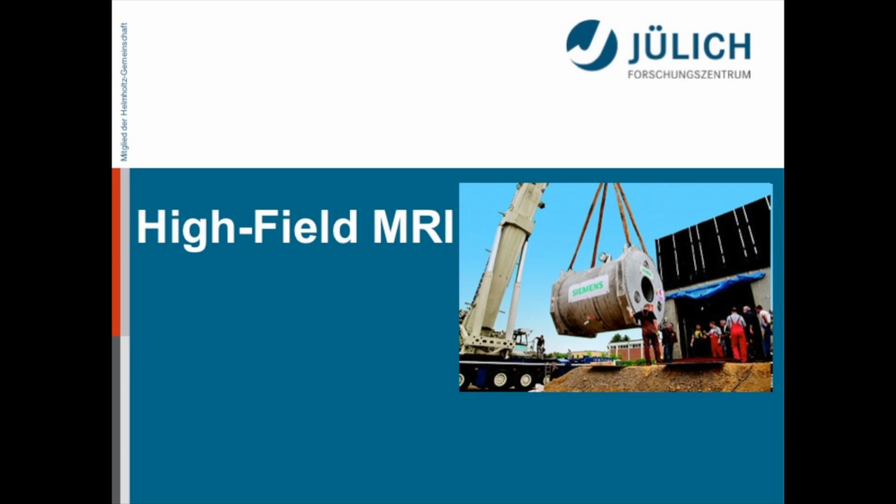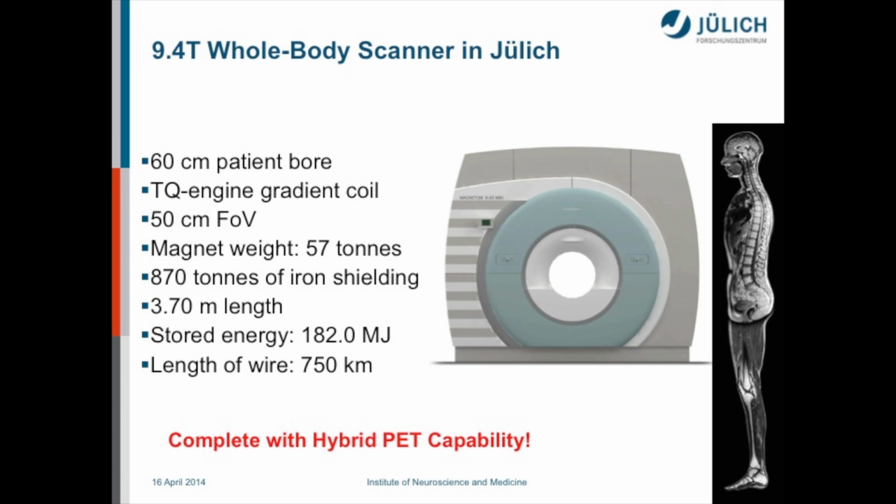So that's, I think, pretty much all I want to say to you about the 3T work. So we have the scanner running. It's been running for about 3 years or so. We've done 600-700 subjects, patients in that scanner. And we're now porting that methodology to high field. This is a 9.4 Tesla magnet on its way into the building. Sadly, it's going to have to come out also because it quenched a few months ago. But nevertheless, we managed to do quite a bit of work on it before it quenched.